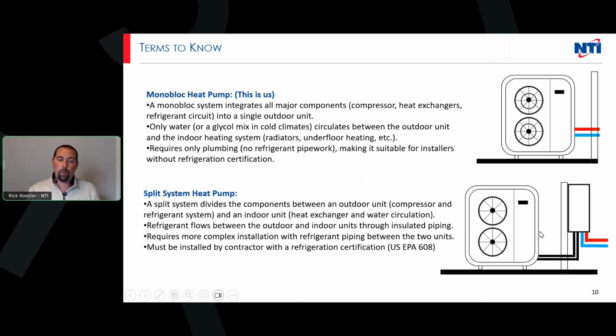Whereas in a split system, we have two components. We have an indoor box, which usually will house a refrigerant-to-water heat exchanger. So we're moving refrigerant from the outdoor unit into that indoor box, and then we transfer that energy into the water indoors. I think this is one of the most confusing parts of these systems. We've heard many times that we don't need glycol if we go in with a split system. That's kind of a false statement; you don't need as much glycol in the system when you have a split system.